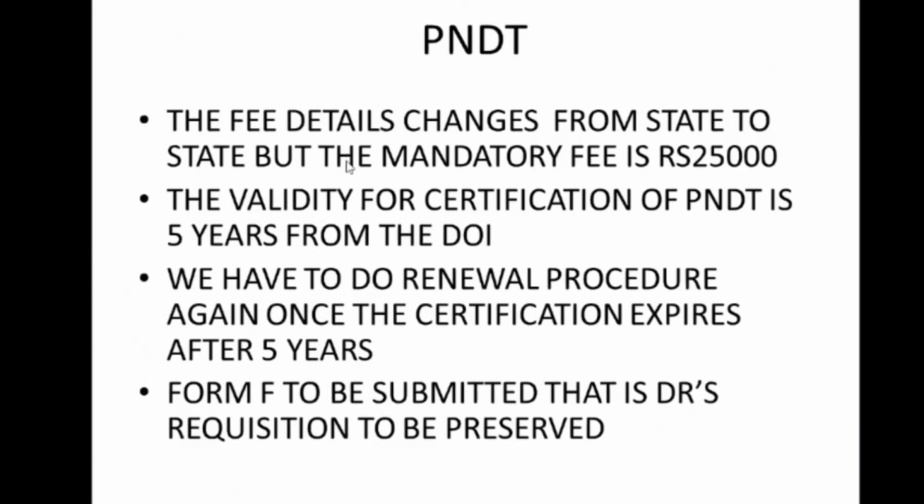The fee details change from state to state, but the mandatory fee all over India is 25,000 that you have to pay to get a PNDT enrollment. And the validity of the certification for PNDT is 5 years from the date of enrollment or date of installation. Whenever you install any ultrasound machine, from that date you have 5 years. Before that you won't have any expiration date. Once 5 years is over, you need to do the renewal procedure.